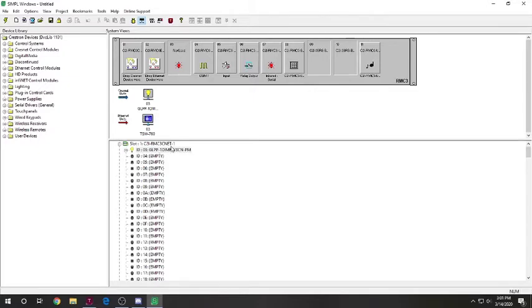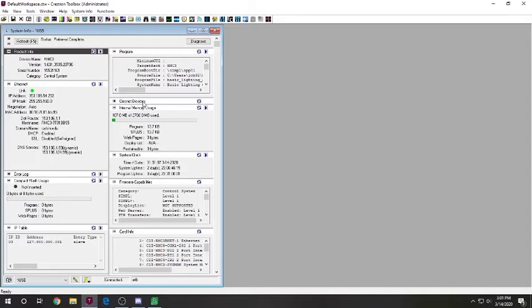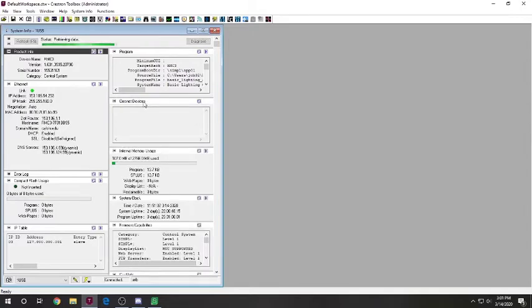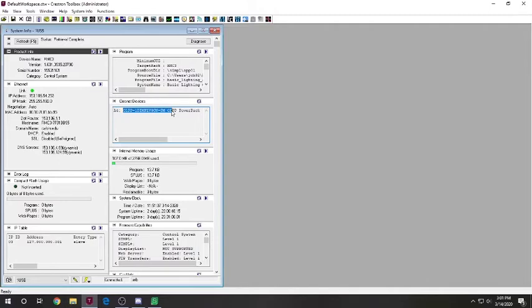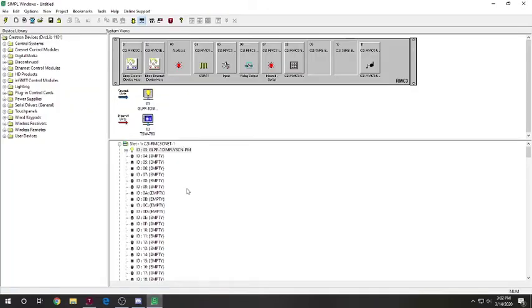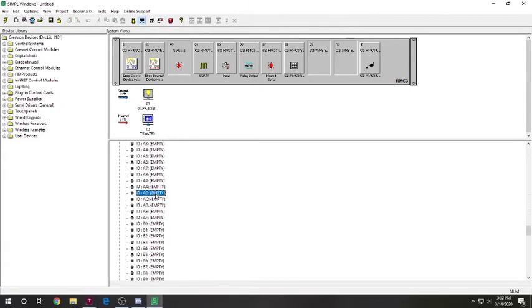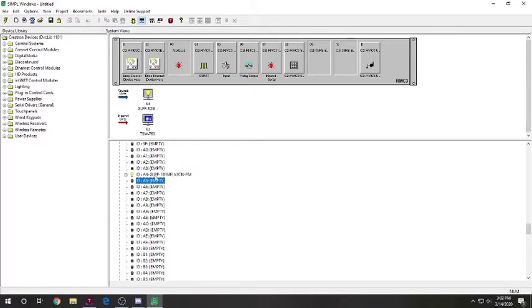If you can't get the exact model number, talk to whoever it is you're working with on this. They'll know more than you will. So, this is the device we want. We're going to enter it in. Now, this is where Mason and I got stuck for quite a while. We're going to open up Toolbox real quick. So, we're connected via USB to the RMC. You see this little tab right here called CrestNet Devices? The lighting controller is connected via CrestNet. So, we're going to take a look at these devices. Now, originally, it didn't show. It just had to refresh. So, here we have our GLP whatever power pack lighting controller. All the information is listed right here. And now, this, this is what we want. That's the port ID. So, we want A4. So, notice here it's on ID 03. So, we're going to click and drag this. And we're going to scroll down all the way to A4. Sweet. So, now that's in the right spot.